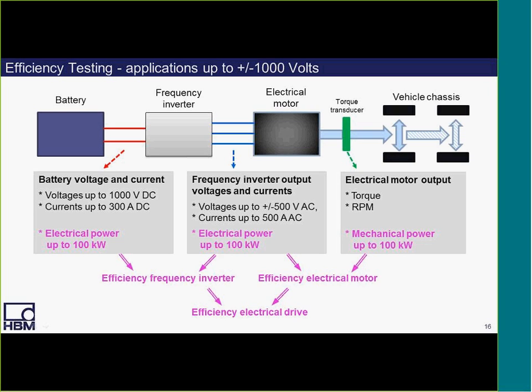So in this efficiency testing example, you'll often need to measure voltages up to 1,000 volts DC from the battery, or currents up to 300 amps from the battery. Or from the frequency inverter or converter, you may need to make voltage measurements up to plus minus 500 volts AC, currents up to 500 amps AC from single or even multi-phase conditions.